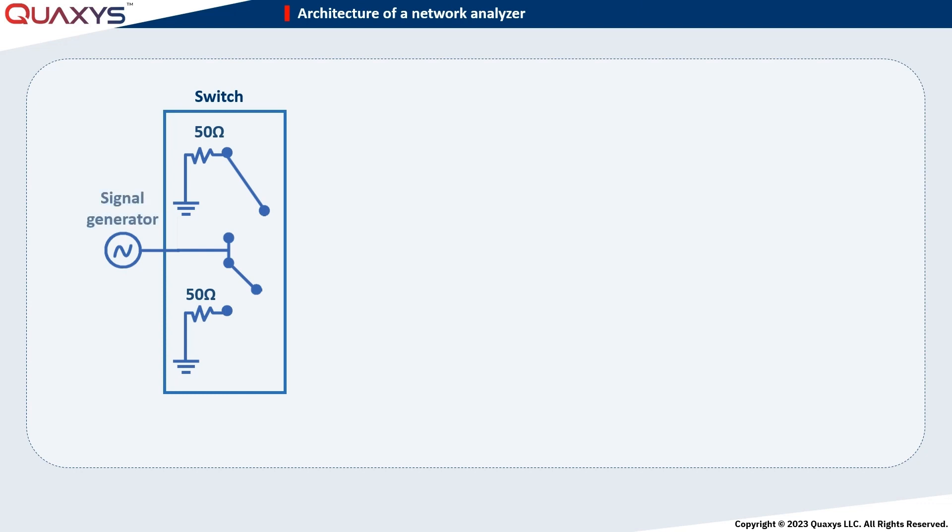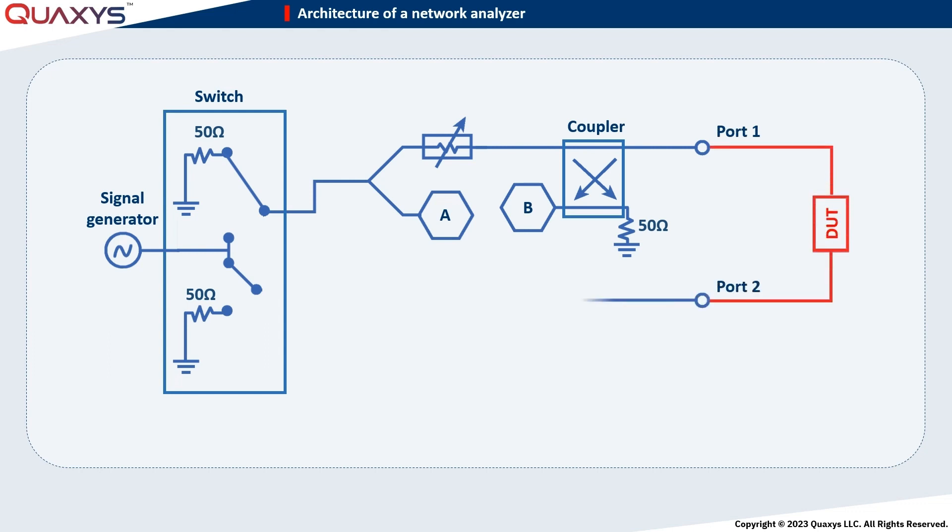Now, focusing on the scenario where the signal is injected into port 2, the generated signal traverses a switch and encounters a power divider, which equally splits the signal between its arms. One arm of the power divider contains a variable attenuator to adjust the power level, while the other arm connects to a detector, referred to as detector C. Subsequently, the signal from the upper arm proceeds through a coupler and interacts with port 2, where the device under test is connected.